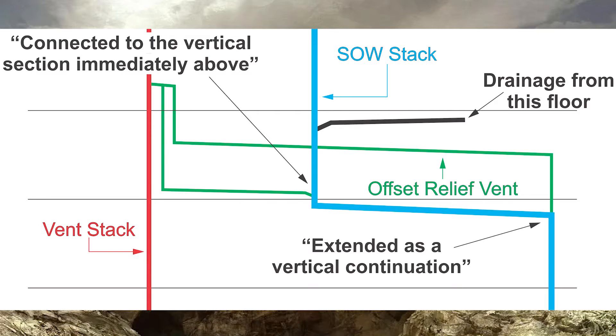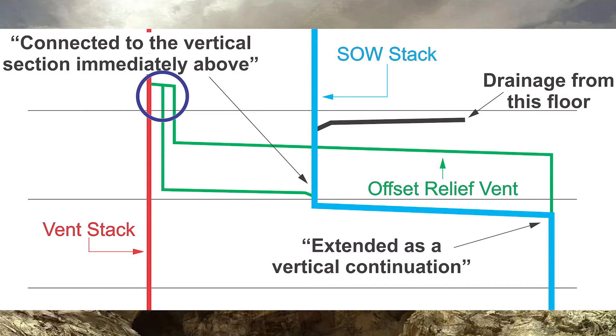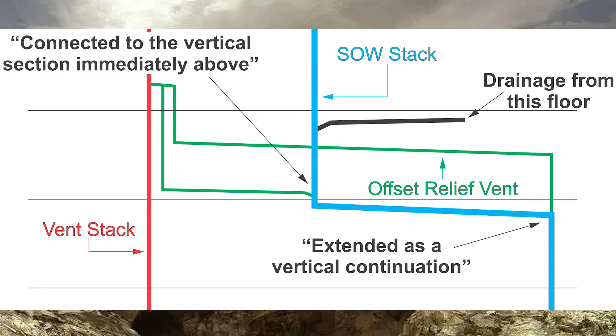The last part is extended as a vertical continuation of the lower section. If I had a Y and that offset relief vent comes straight out of the top of it, and then my offset comes off the side — that's exactly what they're talking about here. Now, a clarification: you might be wondering why I've taken that offset relief vent and tied it together above the floor line. If you look to the right, you'll see the drainage from this floor — I need to be above the flood level rim of that. So that's why I brought it up there. That is code.